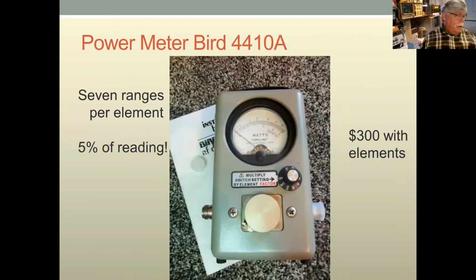Power meter: I've talked about lots of different power meters, and this is the one that sticks with me, a Bird 4410A. Each slug is good for 7 ranges, and you probably only need 2 slugs, and they're not that expensive. If you add up the cost of the meter and 2 slugs versus 14 slugs and a Bird 43, it's a no-brainer. But this one is 5% of reading accuracy, while the 43 is 5% of full scale.